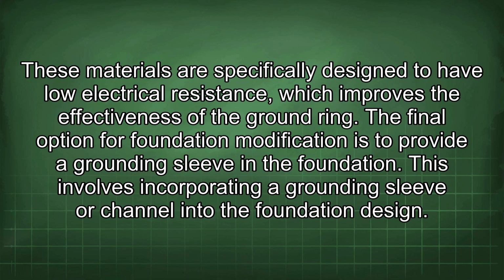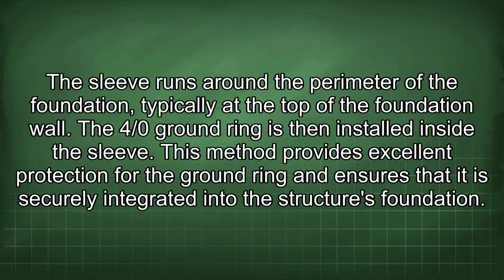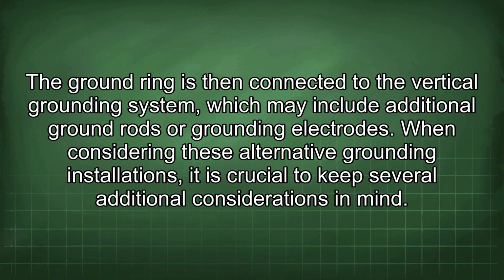The final option for foundation modification is to provide a grounding sleeve in the foundation. This involves incorporating a grounding sleeve or channel into the foundation design. This sleeve runs around the perimeter of the foundation, typically at the top of the foundation wall. The 4/0 ground ring is then installed inside the sleeve. This method provides excellent protection for the ground ring and ensures that it is securely integrated into the structure's foundation. The ground ring is then connected to the vertical grounding system, which may include additional ground rods or grounding electrodes.